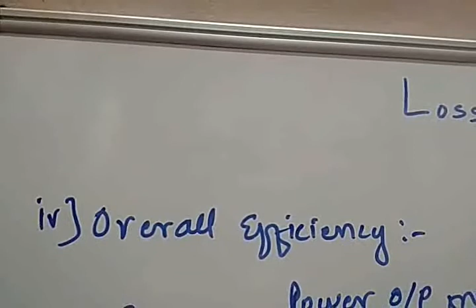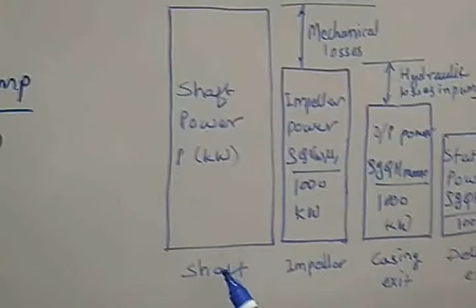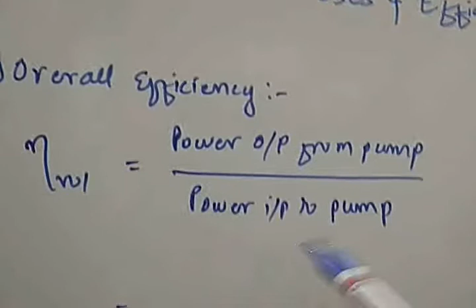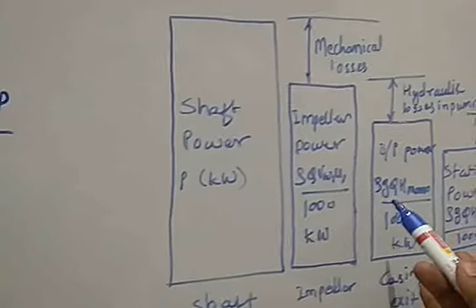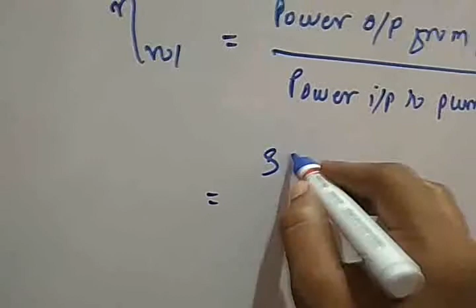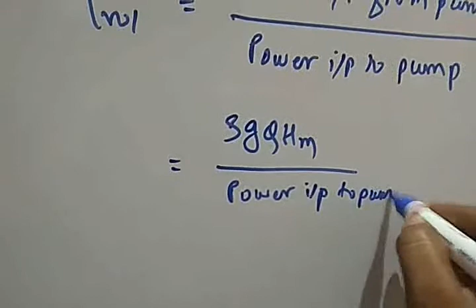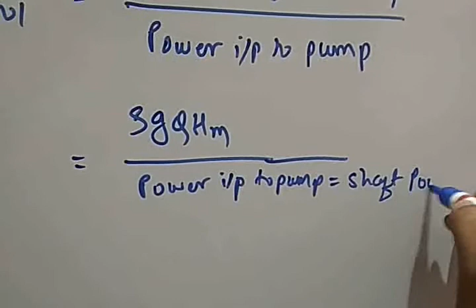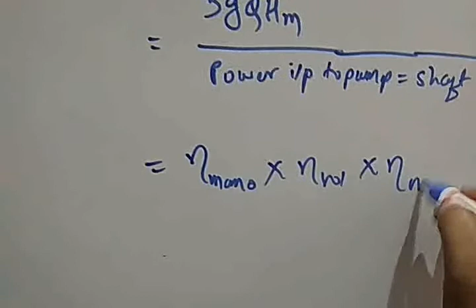The next is overall efficiency. The overall efficiency is the power output from the pump, that is at casing exit, to the power input given to the shaft or to the prime mover. Power output from the pump is rho GQ into manometric head, divided by power input to the pump, which is also known as shaft power. This is also written as manometric efficiency into volumetric efficiency into mechanical efficiency. So this is the overall efficiency.